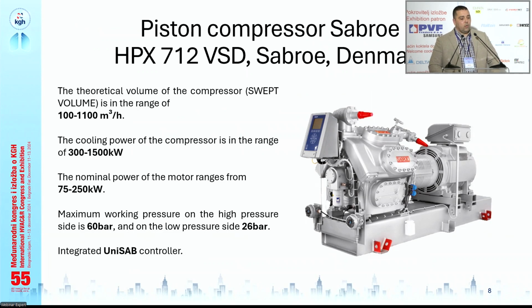It has a theoretical volume from 100 to 1100 cubic meters per hour. It also works in a different range of motors installed. It can work from 75 to 250 kilowatts. On some special applications, the motor can be even bigger, but then we have to put special care on the design of oil cooling. And what is particularly interesting for this compressor, when it works in a heat pump mode, is that on the high side, it works with operating pressures up to 60 bar.